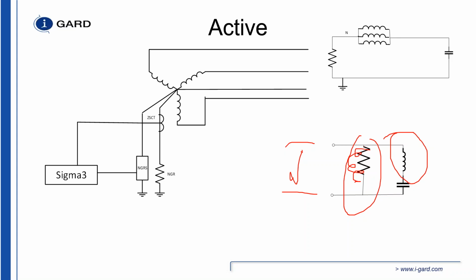And then you don't have to have any setting for the NGR, for the resistor monitoring, because in passive mode, we can pick up if that resistor changes greater than 70% or 150% of the rated value. In active mode, depends on the voltage.